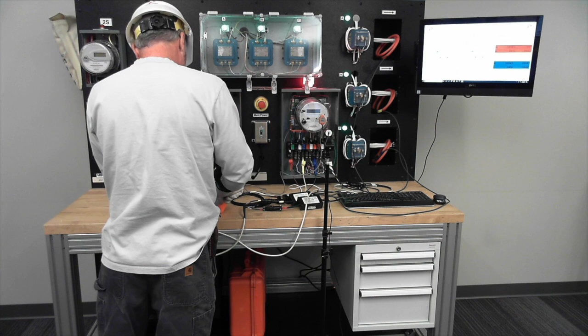What I'm going to do is a CT ratio test where I'm going to compare these secondary currents with those primaries over there, and we're going to see how close it is to 200 to 5. So I'm going to check.